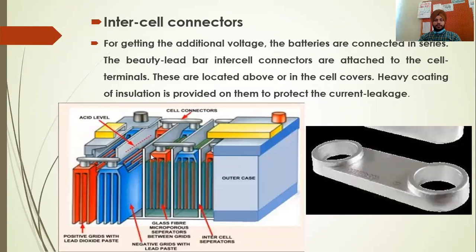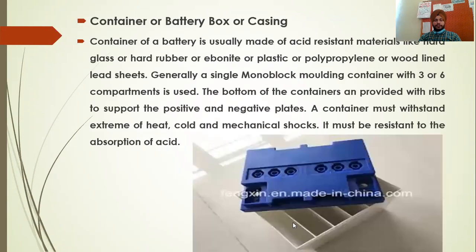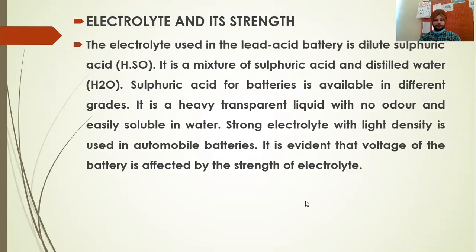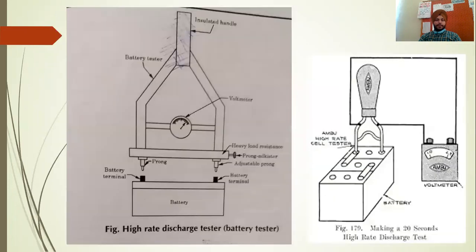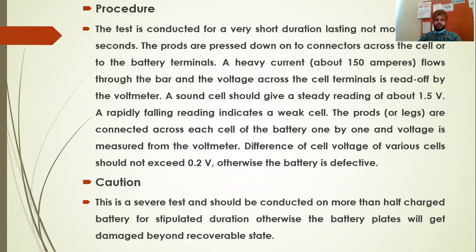Here is one cell and the other cell. There are a number of plates that we group. We need to check every cell. When we check every cell, each cell should not be more than 0.2 volts difference. If there is a difference between cells, that indicates the battery is defective. If reading is reduced, the battery has less charge.